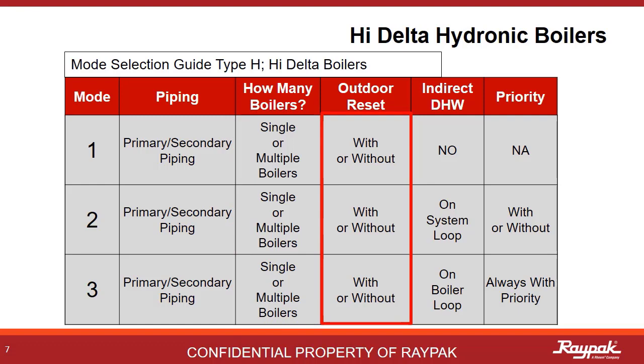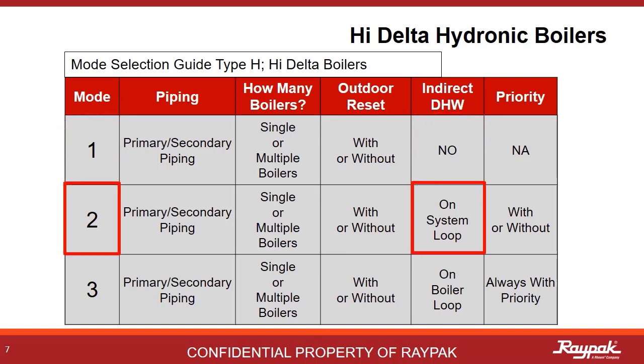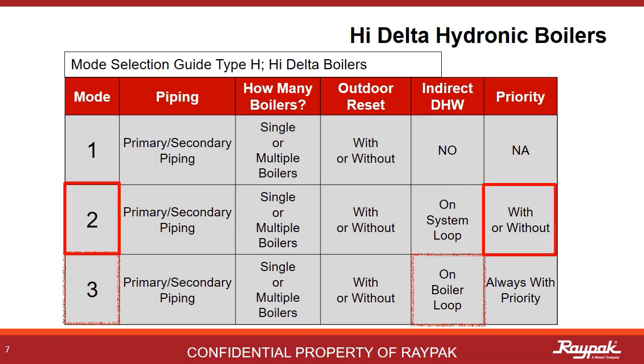The difference lies in the presence or absence of an indirect hot water system. If there is no indirect, then it is Mode 1 — this is the most common configuration. If there is an indirect system present on the system loop, then it is Mode 2. If the indirect is present on the boiler loop, then it is Mode 3. Mode 2 can be run with or without priority, while Mode 3 is always with priority.